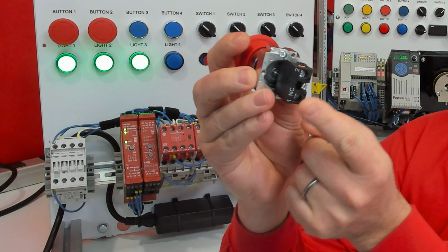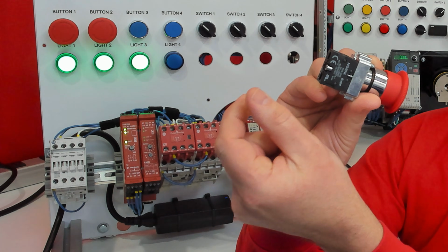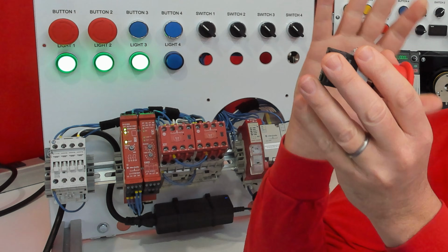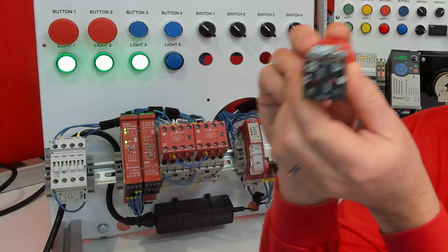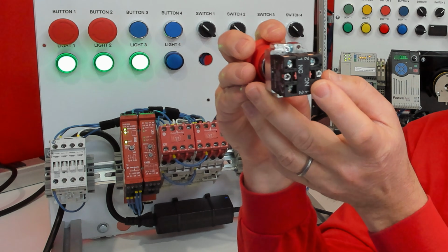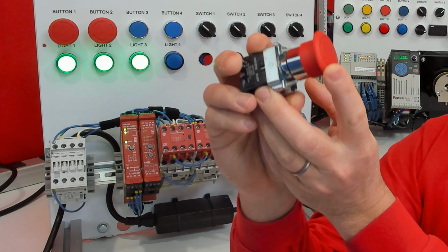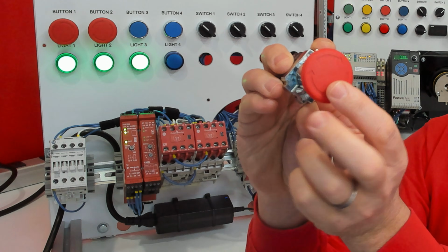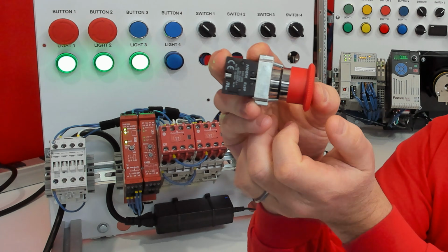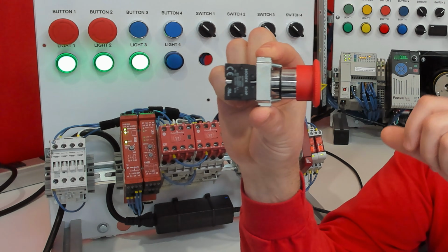But this is a single point failure because this contact could get stuck. Also, the whole contact itself could just pop off the back of the block. And being normally closed on typical E-stops, it will not sense that that contact is off. So simply by adding a second contact to the back of this E-stop, we're going to reduce the likelihood of a single point failure. Now, before we even talk about the single point failure, let's look a little closer at the E-stop. You'll notice it has some symbols on it that tell you to twist it to release it. So you press the E-stop, that's going to lock it in. In this case, you twist it, and that's going to pull it back out.